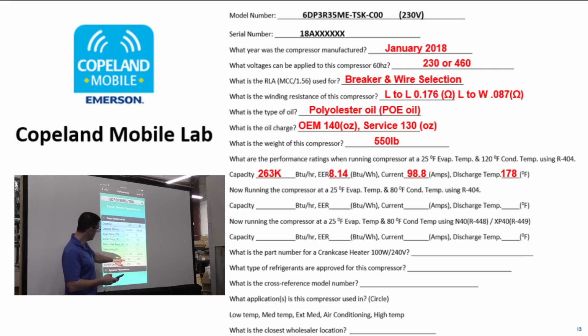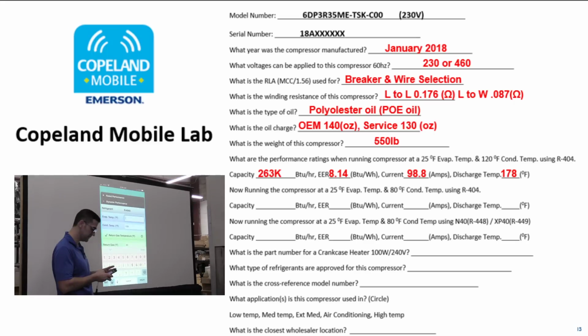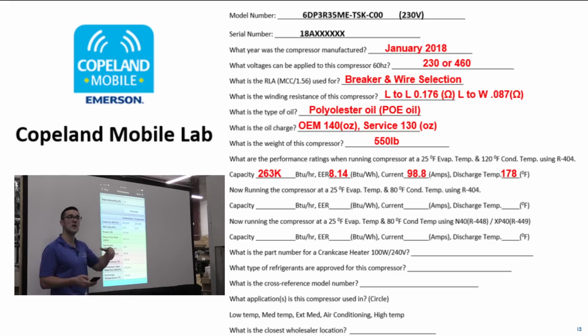So, if you go down to dynamic performance here, you can change things. What I want to do is change the evap temp to 25. And then the condensing, well, I'll leave it at 120. Just go down and press calculate. And now these are the new conditions. 263 and 98.8 amps. So now you can put your gauges on that system, put this information in there and see if this compressor is working efficiently or effectively. And this is the amount of BTUs you should be getting out of that.